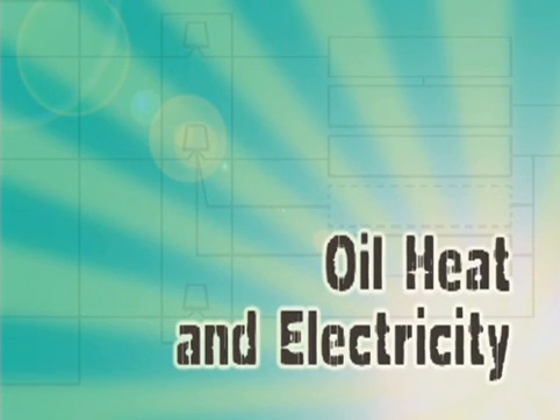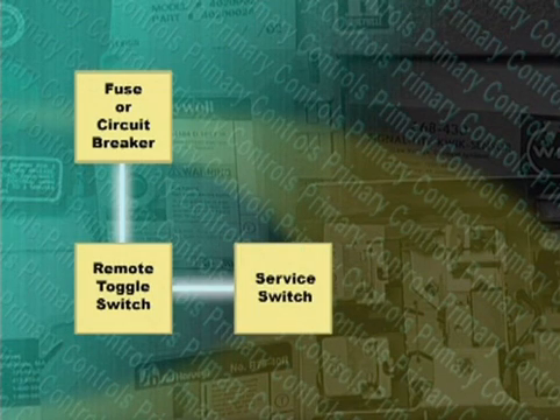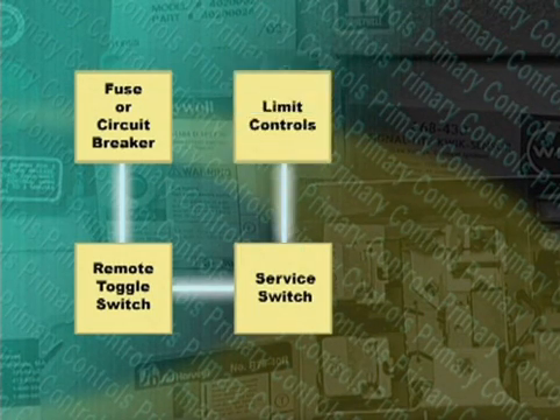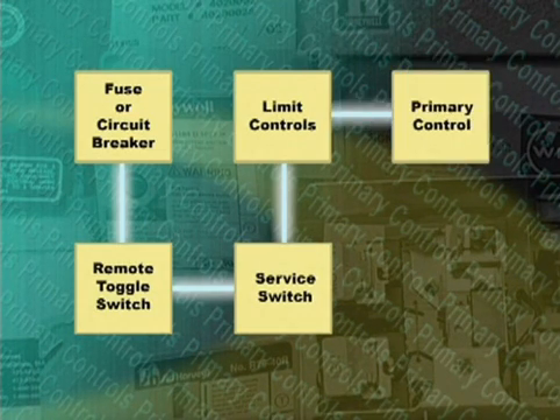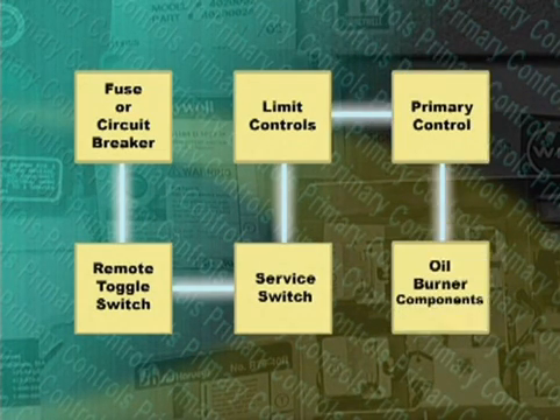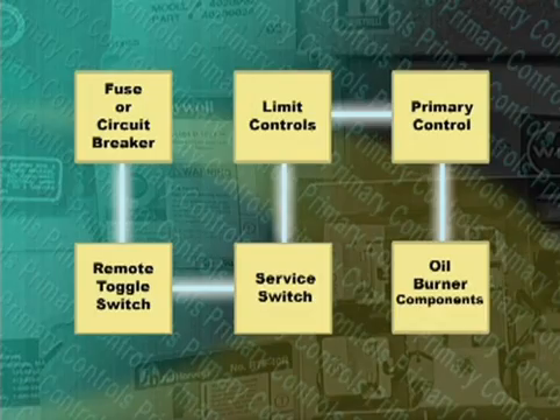We'll start by discussing oil heat and electricity. Oil heat systems require electricity to operate. In a typical system, line voltage flows in a series circuit from the fuse or circuit breaker to a remote toggle switch located away from the heating unit. From there, it continues to a service switch at the oil-fired appliance, next to the limit controls, and then to the primary control, which distributes power to the oil burner components to manage the combustion process.